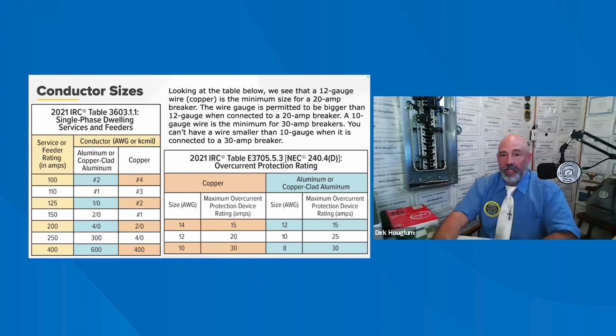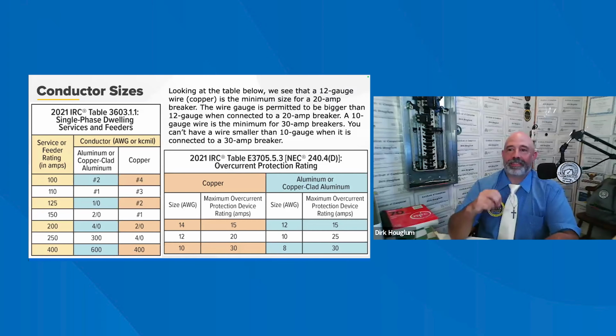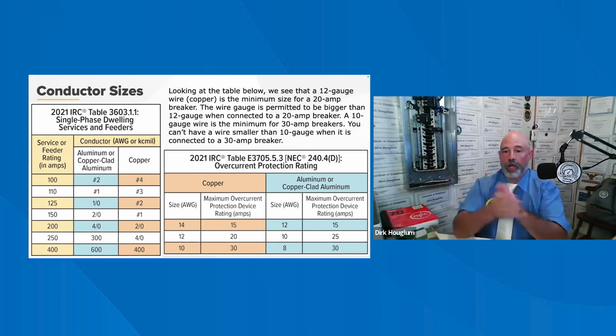Hope that made sense. As we saw with Ohm's law, resistance is key to a conductor's ability to safely deliver the amount of power that the circuit needs. Think back to that pipe. The bigger the pipe, the lower the resistance. So when you're evaluating an electrical supply, we need to recognize that copper and aluminum conductors are not the same. Although they are both commonly used in residential supply, copper inherently has less resistance to the flow of electrons than aluminum does.